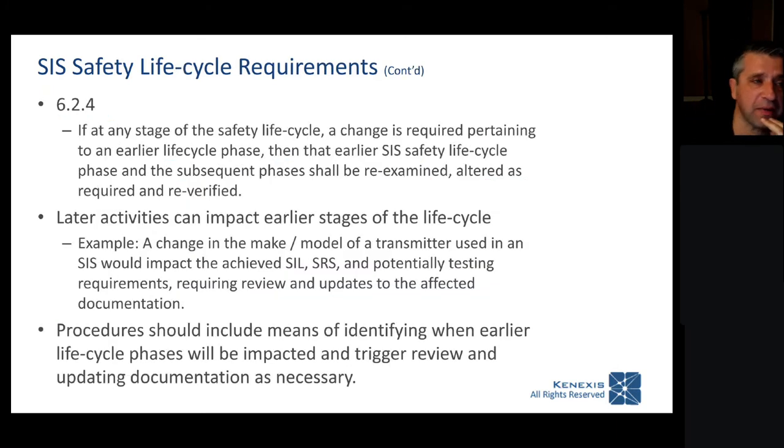Okay, going on a little bit further in clause 6.2.4, we state that if at any stage changes are required, once you make a change, you need to follow an elegant management of change process and procedure that is going to ensure that your safety integrity level and tolerable risk is achieved after the design changes are put into effect.